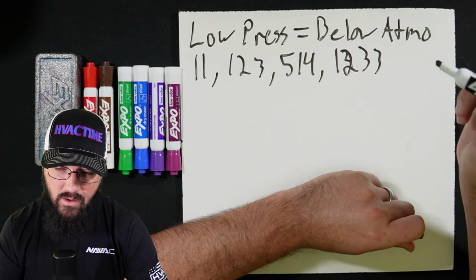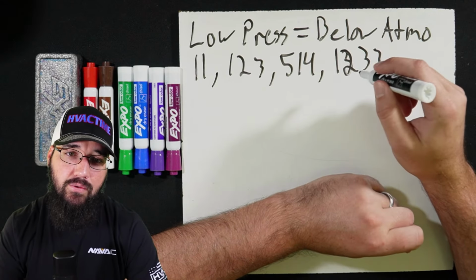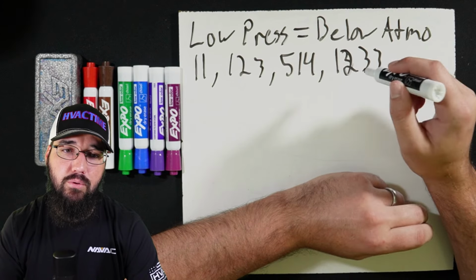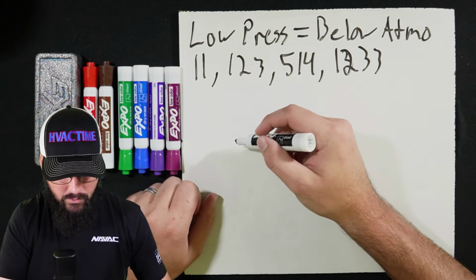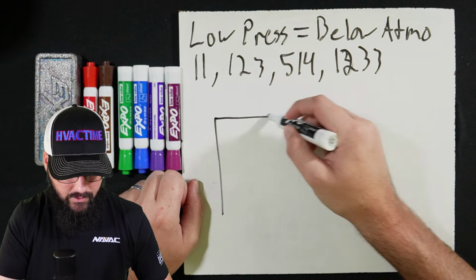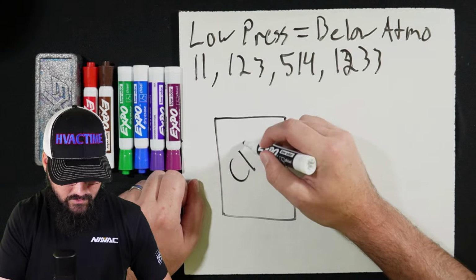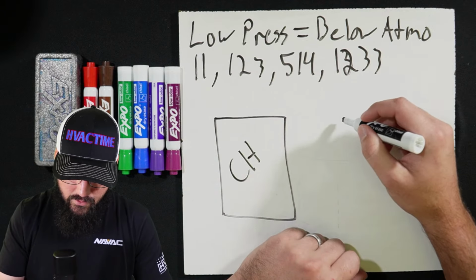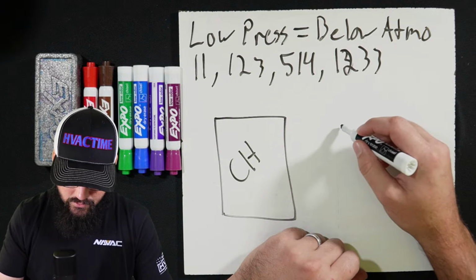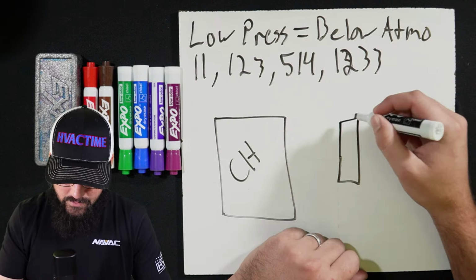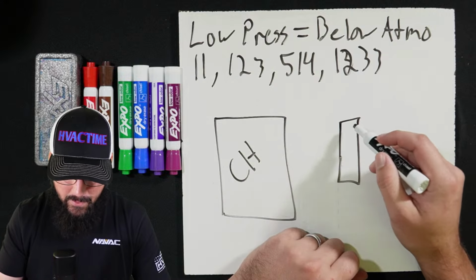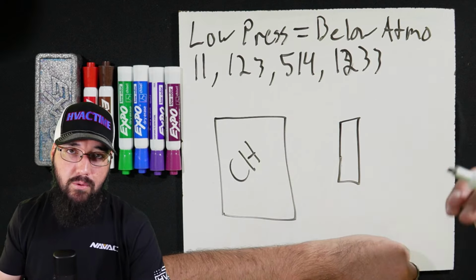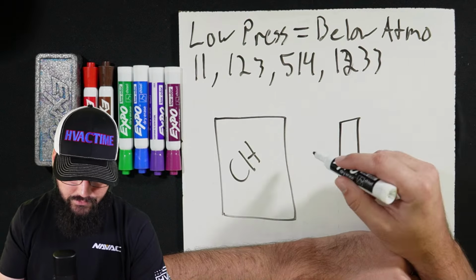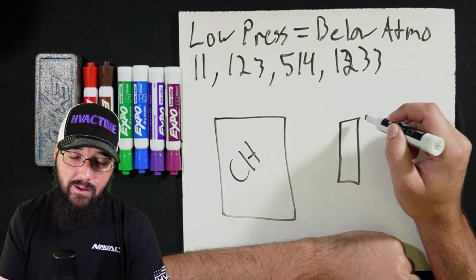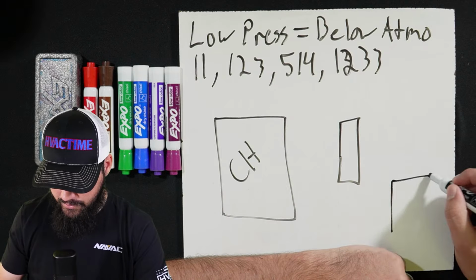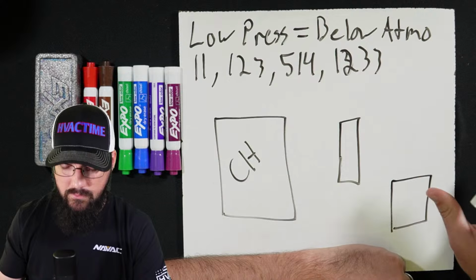So the most efficient way to transfer this refrigerant is going to be a push-pull setup. To do a push-pull, we've got our chiller, we're going to say CH. What we'll end up having is our recovery cylinder, whatever size, it doesn't really matter. But we want to make sure that it's a proper recovery cylinder with 2 valves, so we have a liquid dip tube and a vapor. And we're going to have our recovery machine. It doesn't matter if you're using the Navac or RefTech, that part's irrelevant.